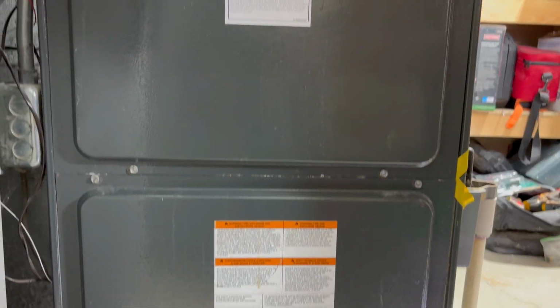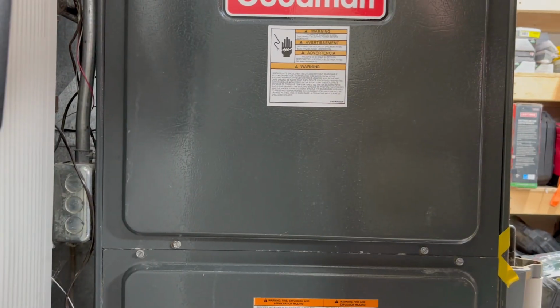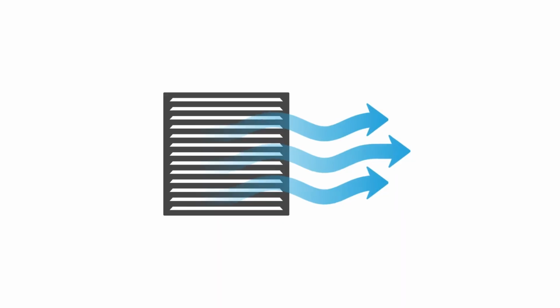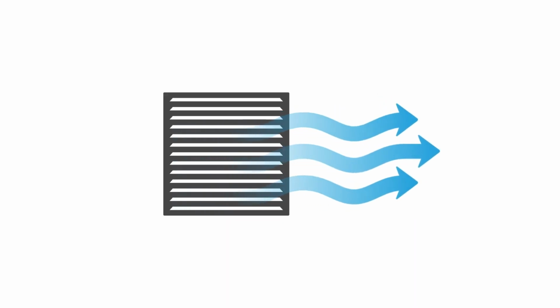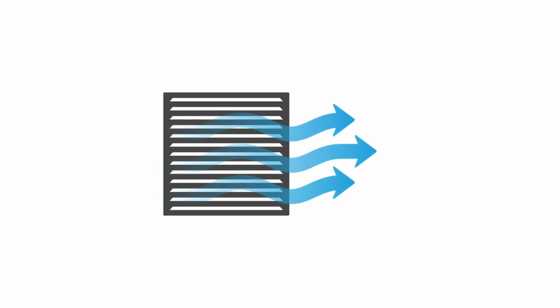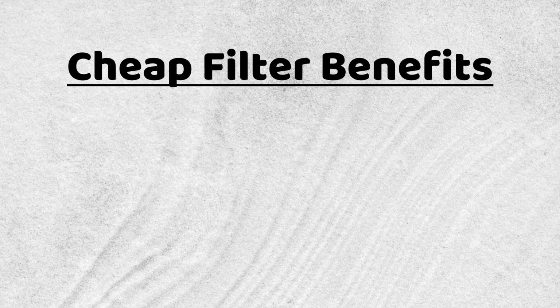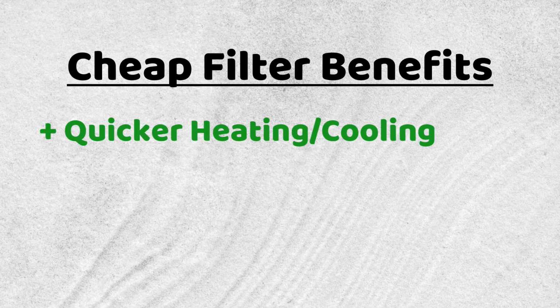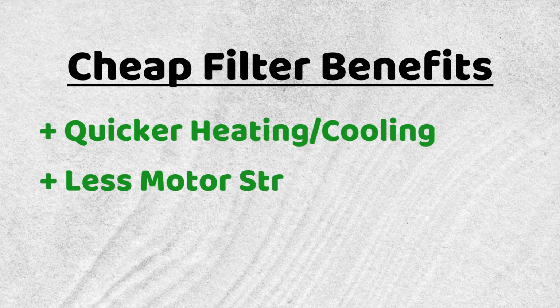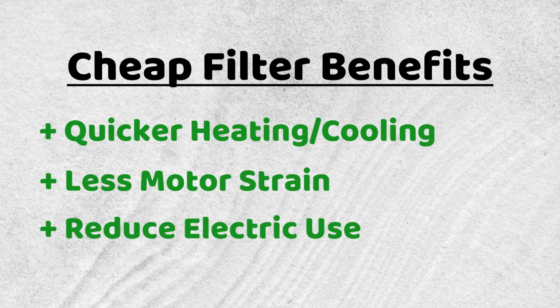And even without factoring in my HVAC system's specific constraints, the testing does go to show that these cheaper filters do improve airflow and can help with furnace performance. And with the higher airflow that we're getting from the cheaper filter, this is going to help keep rooms heated evenly. It's going to reduce strain on the furnace blower, increasing longevity of it, and it may also reduce the energy bill. However, like anything, there are some downsides.